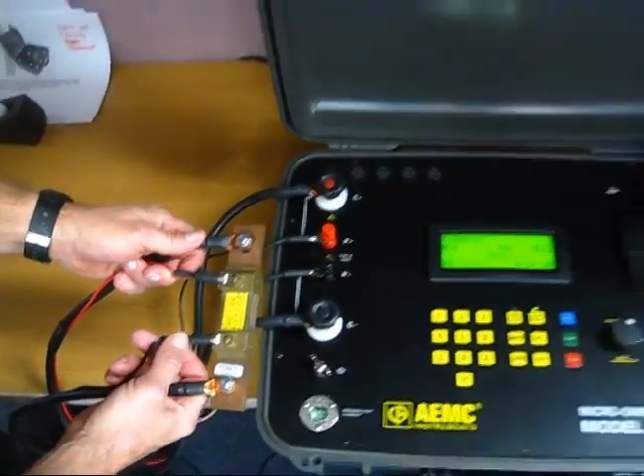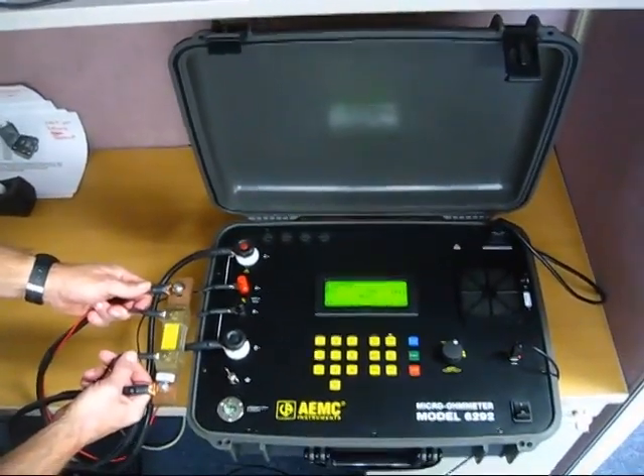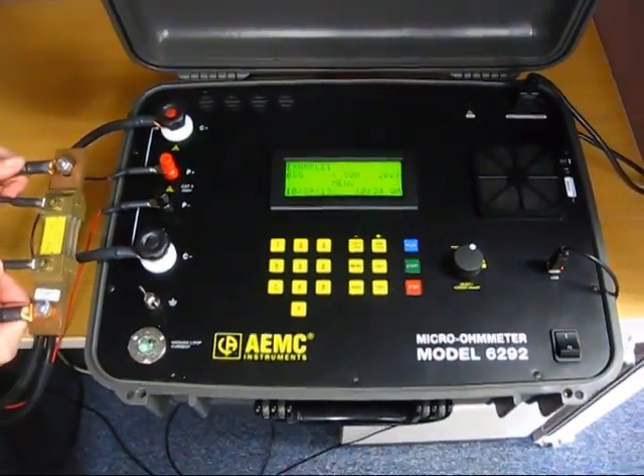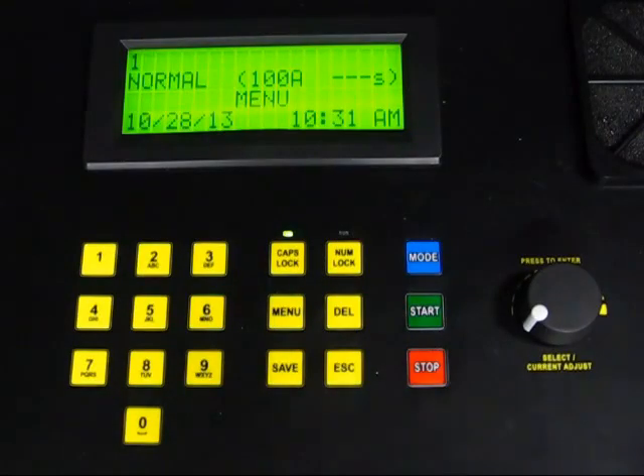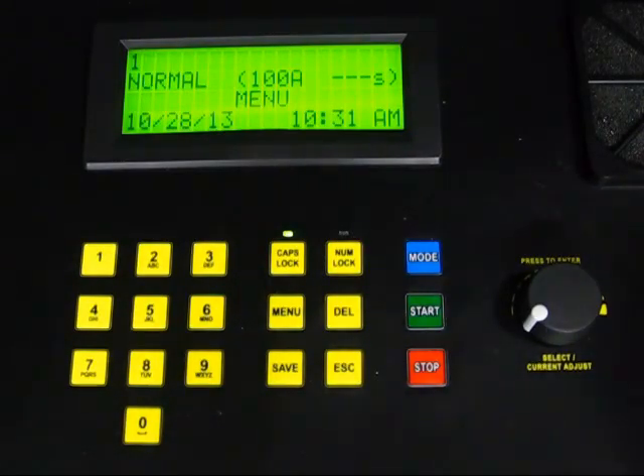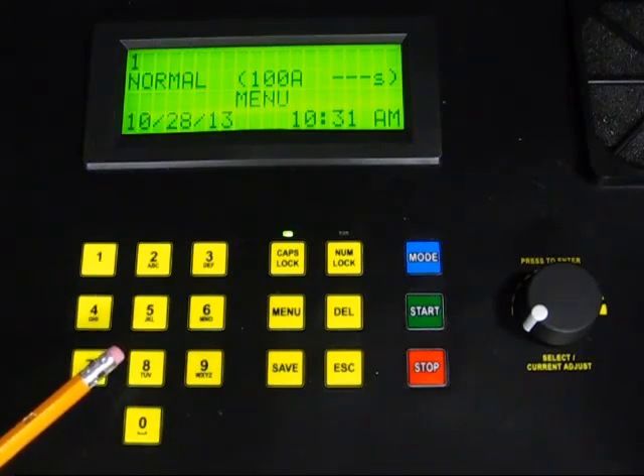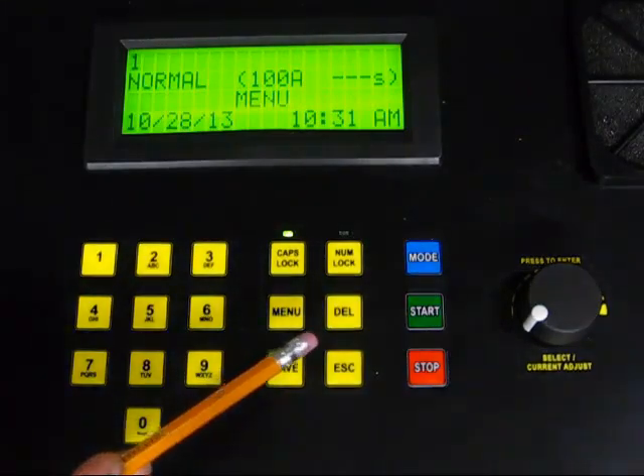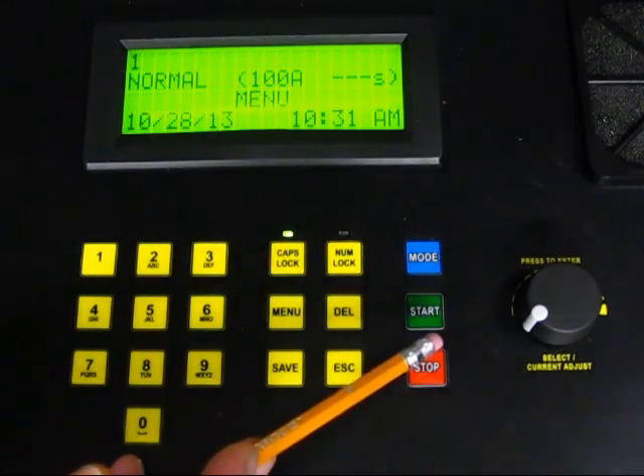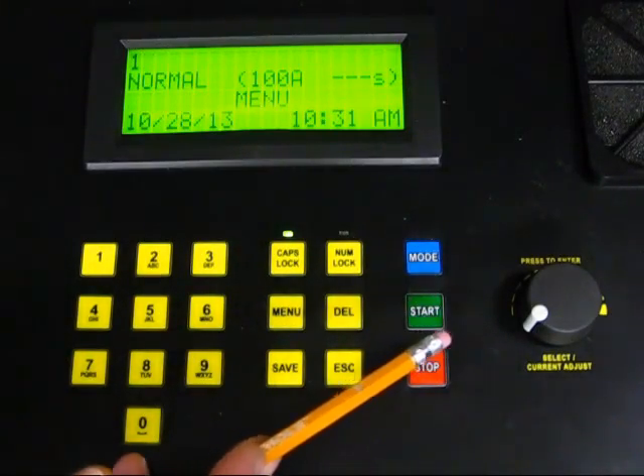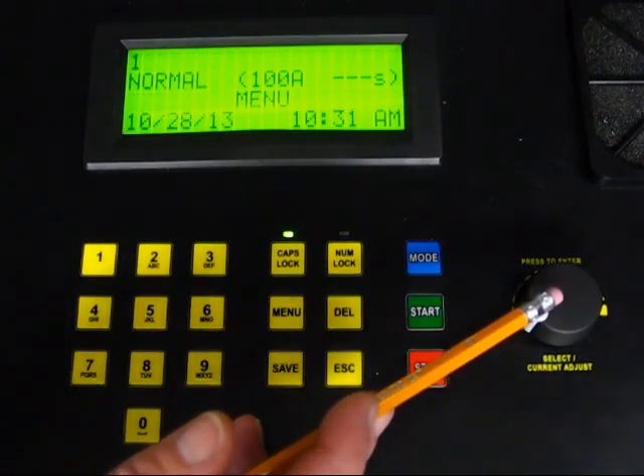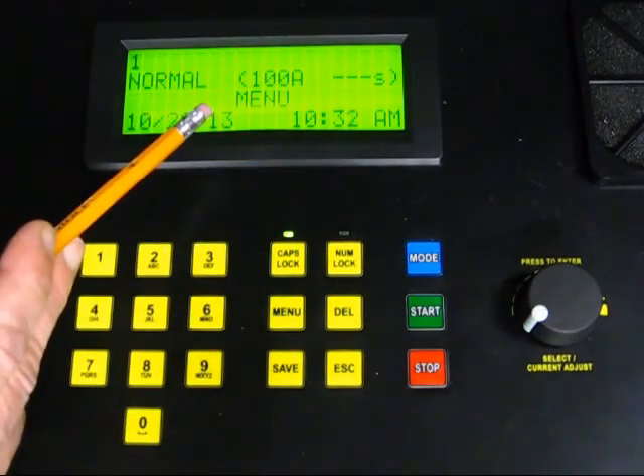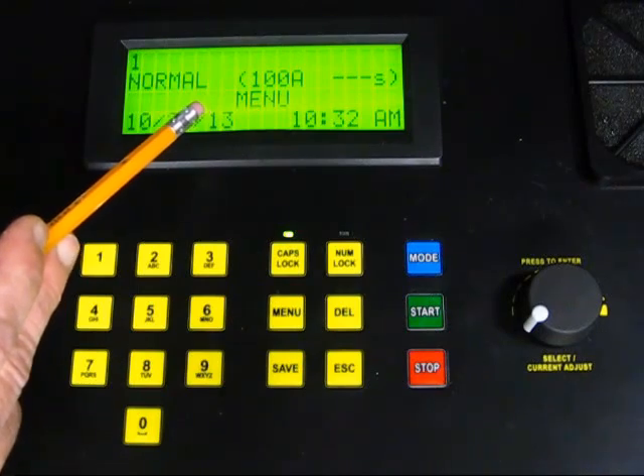For this test, we will run a 20 second test in normal mode with a current of 50 amps. During this test, we will take partial measurements at 5 second intervals and store the results in the instrument's internal memory. The instrument's front panel interface includes an alphanumeric keypad for typing in information, function keys for displaying and working with system options, and buttons for starting and stopping tests and for selecting the test mode. There is also a rotary knob for navigating through and selecting menu options and for adjusting test current during manual mode testing. All information is displayed on the instrument's large LCD display screen.